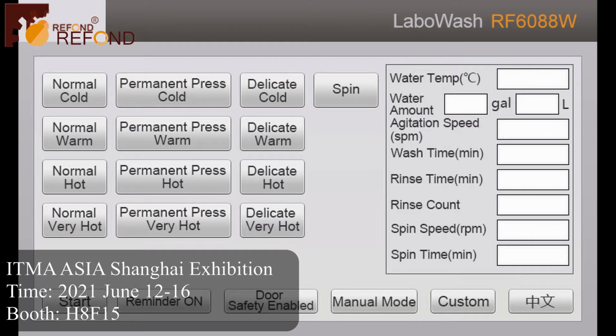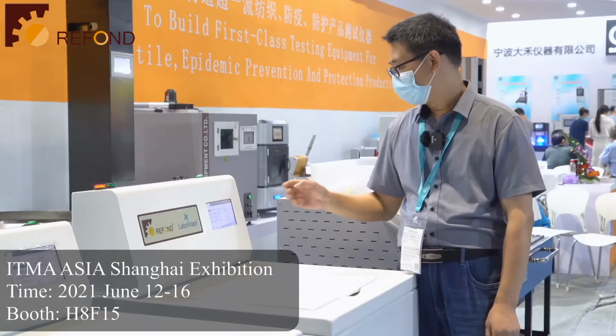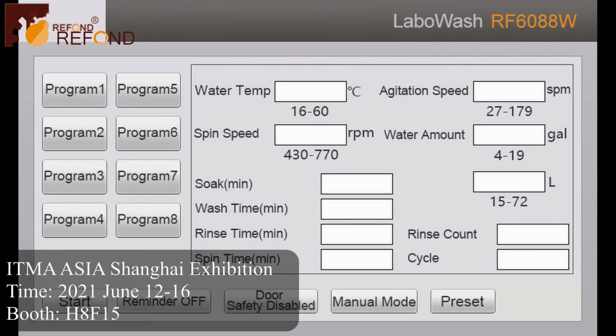has built-in standard testing programs, and in addition, we also have the customer program. The customer can set their own testing programs. They can set the water temperature, water level, the agitation speed, the spin speed, agitation time, and the spin time.